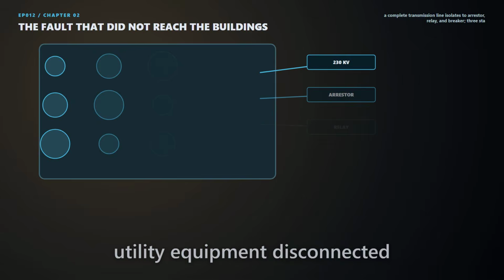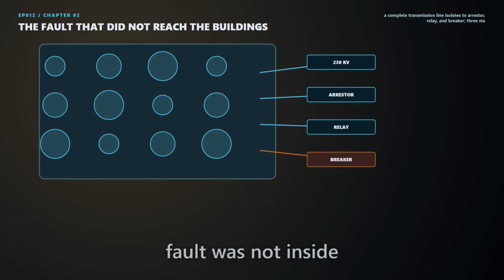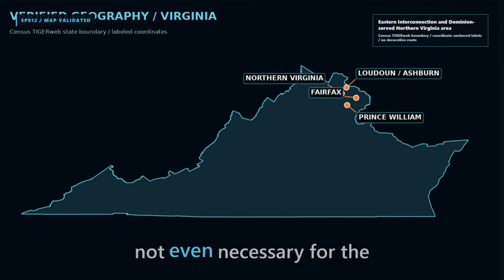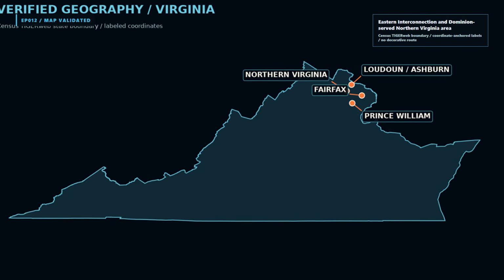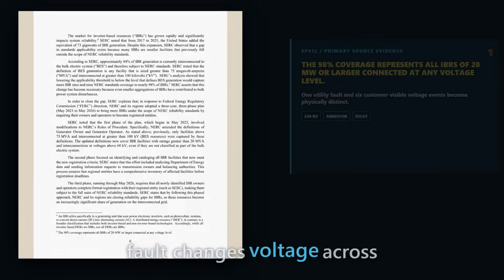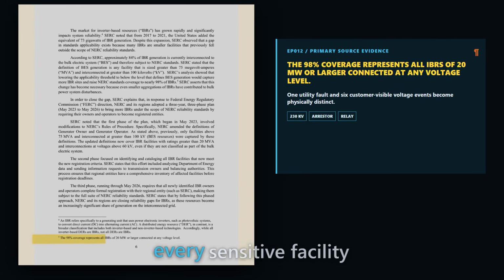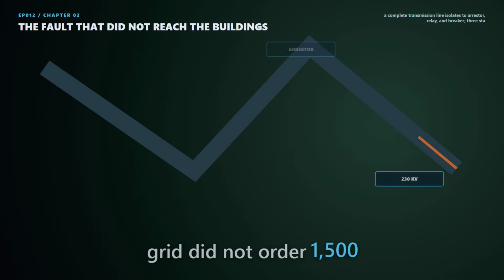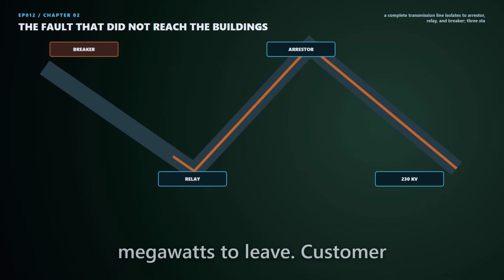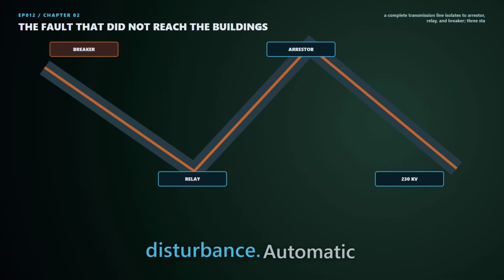No utility equipment disconnected the data center load. The fault was not inside a server hall. It was not even necessary for the line to feed a particular building directly. A fault changes voltage across an electrical area, and every sensitive facility connected to that area can see the disturbance. The grid did not order 1,500 megawatts to leave. Customer equipment responded to the voltage disturbance.